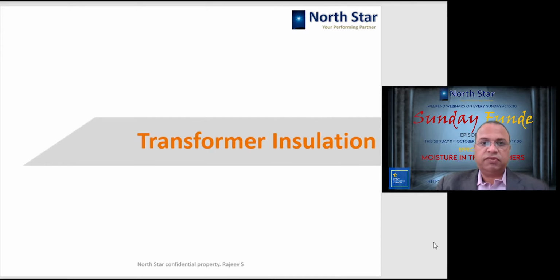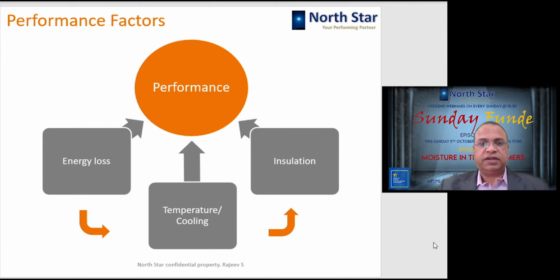So let us look at what transformer insulation is. As we have seen in our last program, transformer performance depends upon three major factors. One is the loss, or energy loss, in the transformer. Then, at what temperature the transformer is working, or how effective its cooling is, decides its performance. And of course the insulation quality, insulation condition, and insulation type being used in the transformer. These three factors are interconnected with each other, and cumulatively they affect the performance of the transformer.